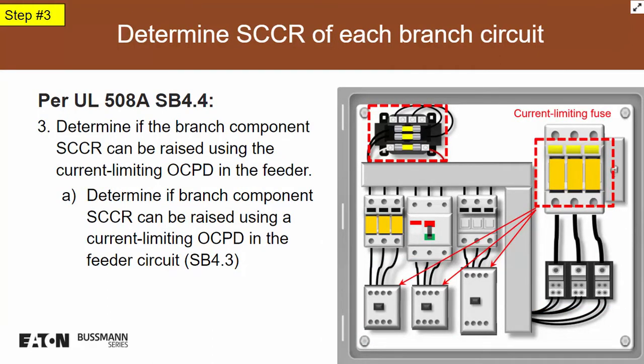Now let's look at step number 3. Step number 3 gets a little bit difficult, and I'm not getting into the details of how to determine it, but we want to give you an idea of what the SCCR is and how you do a quick determination of it, and then we can expand on that down the road. In general, step number 3 is my main or my feeder device. We look at the feeder device: is the feeder device current limiting? In this case, we put an example where we're using a current limiting fuse on the main. The main, in this case, is considered a feeder device. Basically, it feeds a power distribution block, which is in the feeder circuit. So I can't change that device.